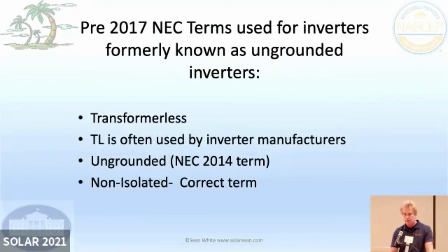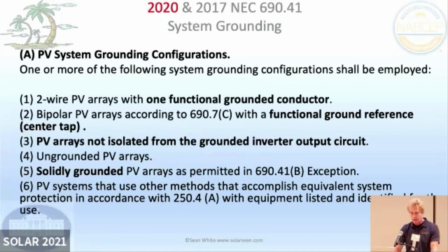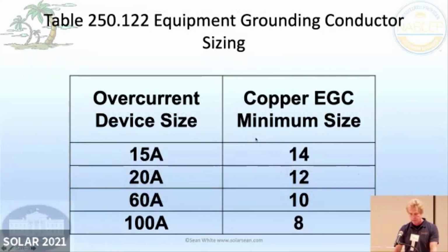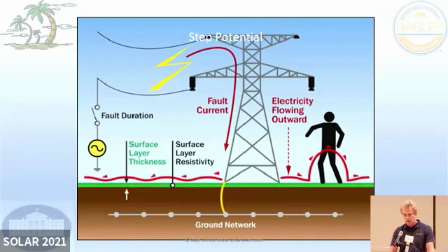So we talked about these inverters that were ungrounded and grounded. Ungrounded inverters, transformerless inverters, that was an old NEC term. Now we can just call that non-isolated, which is a correct term for that, or just call it an inverter, because almost every inverter is that way anyway. And these are the different configurations that we have. One functionally grounded conductor, that would have been what we used to call grounded, fuse grounded. Not isolated, number 3, that's mostly what we're using. And just for grounding, you size your equipment grounding conductor based on the size of the overcurrent protection device. I always thought this was kind of interesting.